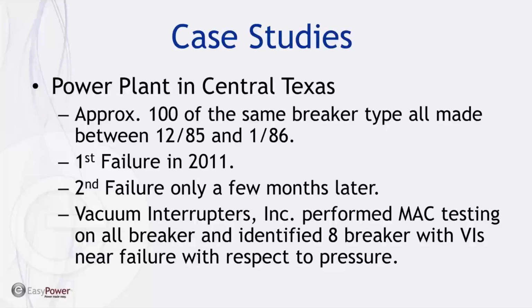And we spent several days at the site, and we tested every single one of these circuit breakers. And what we found was that there were 8 of those circuit breakers which the MAC test identified as having high pressure and being near the failure point. And so those were tagged for replacement, and spare breakers were put in their place. And as far as I'm aware, they have not had any additional failures.